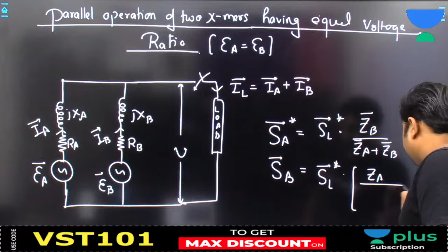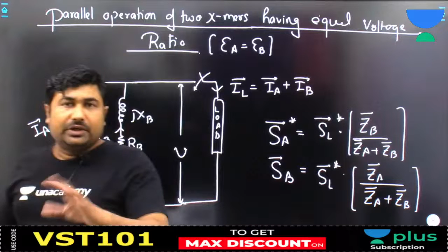We have calculated the KVA delivered by each transformer operating in parallel when the total load KVA is SL. Already derived: KVA delivered by transformer A is SL into ZB upon ZA plus ZB, and SB equals SL conjugate into ZA upon ZA plus ZB, keeping in mind that ZA and ZB are in actual ohms or in per unit on a common base.